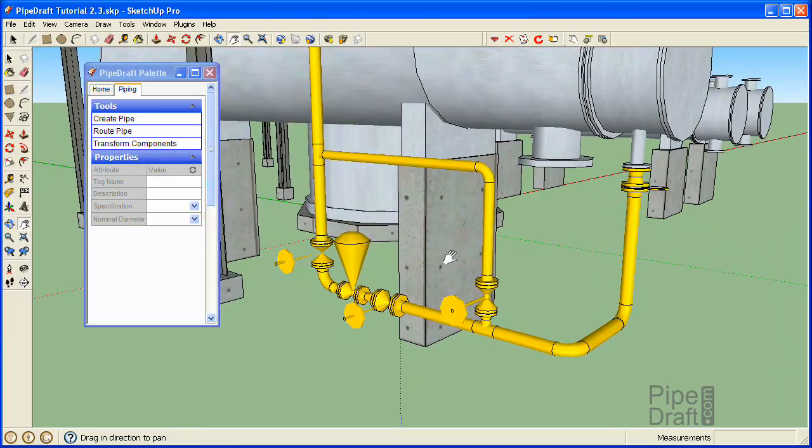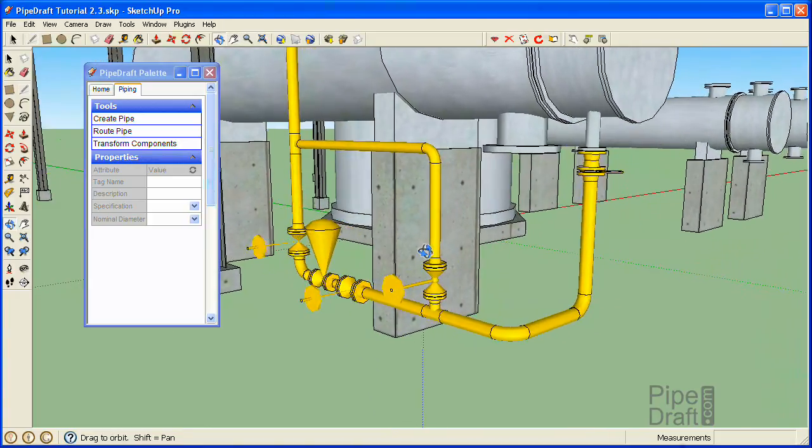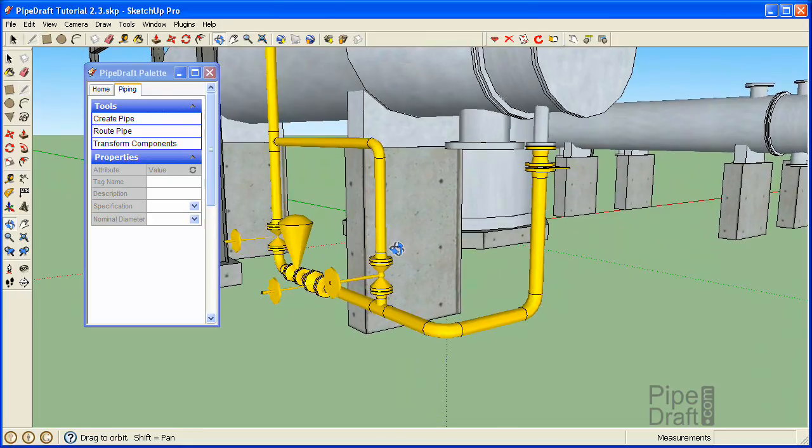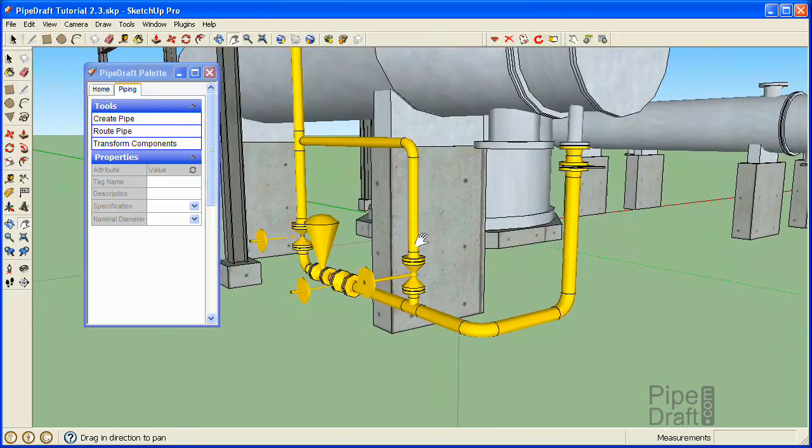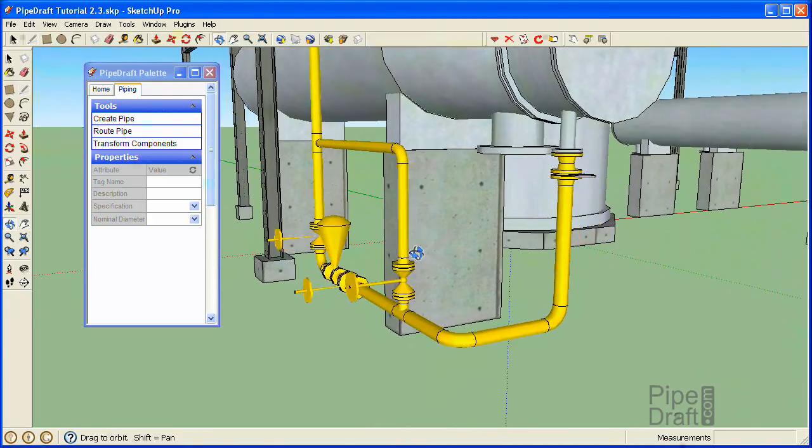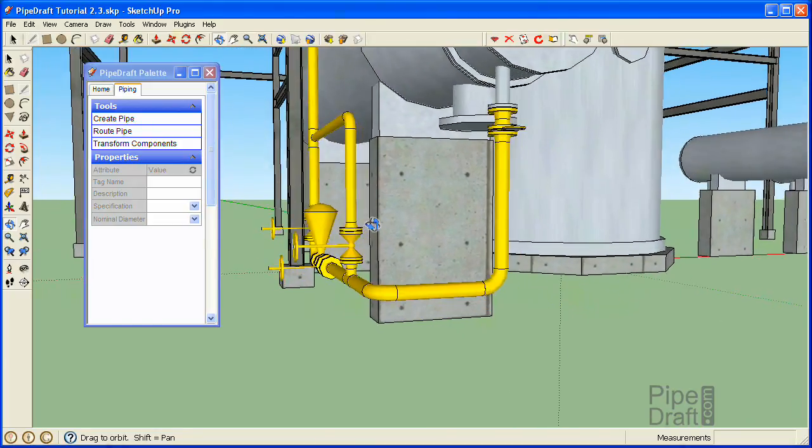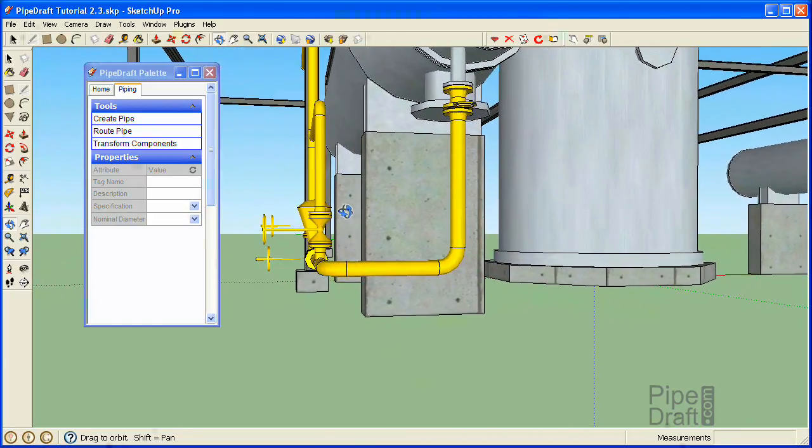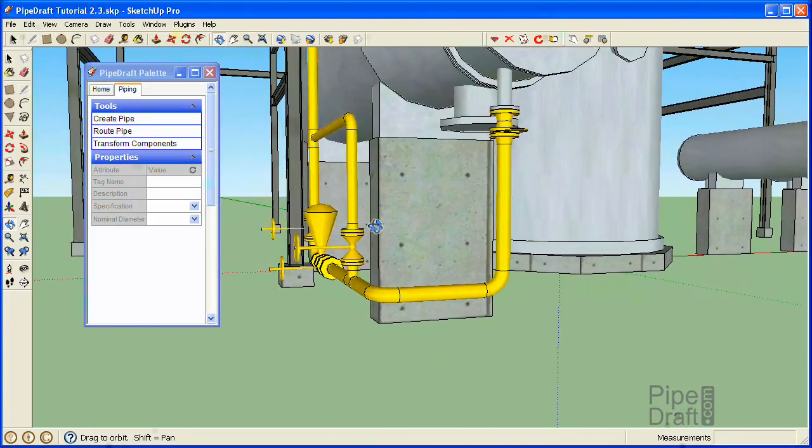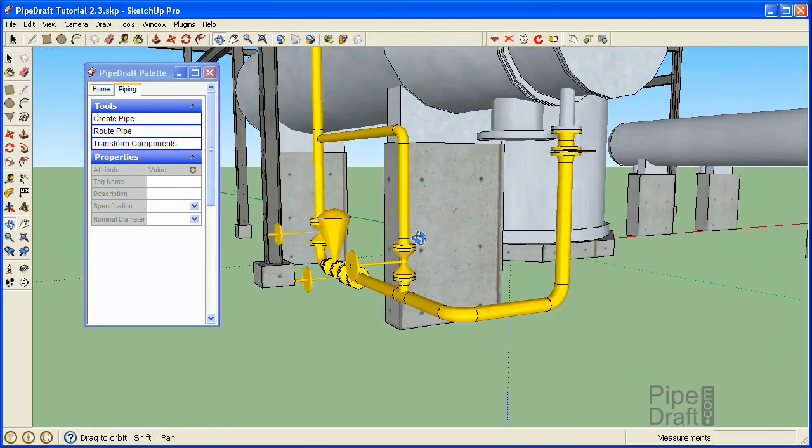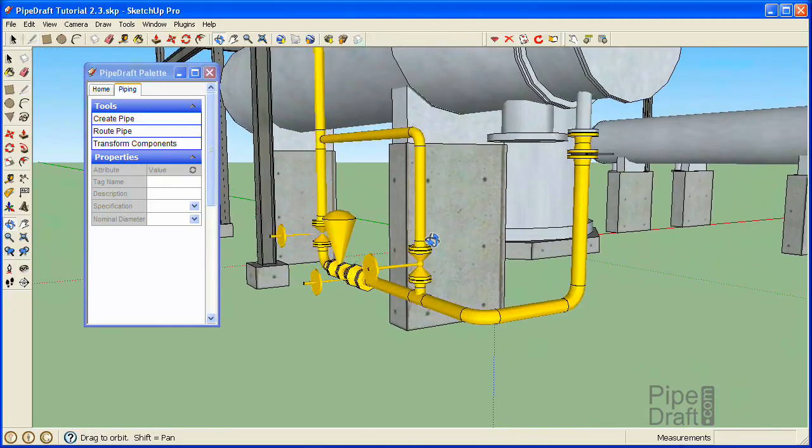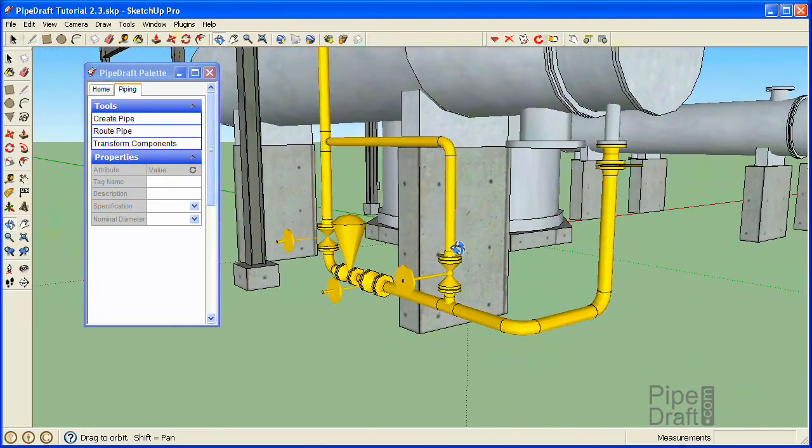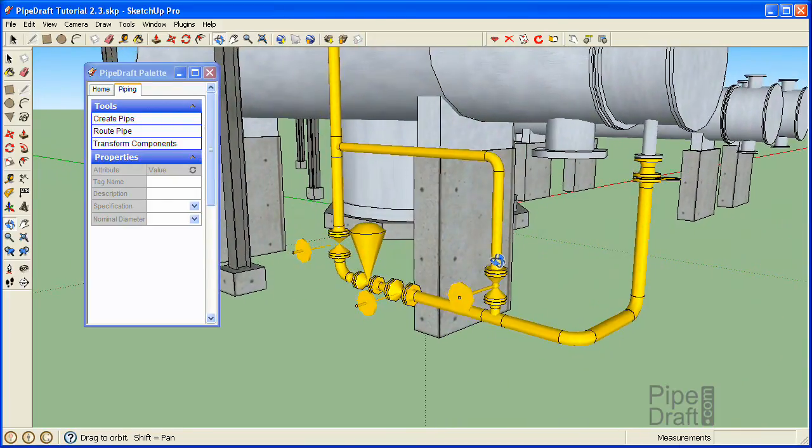Let's examine our control station pipeline for ways that it could be improved. The first thing we notice is that the valve hand wheels are protruding into the access way along the west side of the reboiler. Let's rotate the valves so that maintenance equipment and plant personnel don't get snagged by these hand wheel stems.